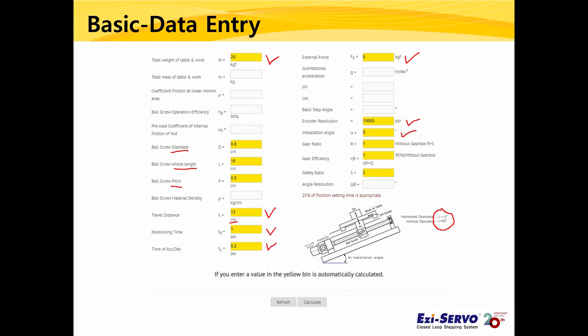This example does not use a gearbox, but if you do, you can enter the gear ratio. Enter 10 for a 1:10 ratio, and 18 for a 1:18 ratio. For gear efficiency, a planetary gearbox is generally 90%, so enter 0.9. A two-stage planetary gearbox would be 0.9 × 0.9 = 0.81. A worm gearbox has a general efficiency of 50%, so enter 0.5. Since this example has no gearbox, enter 1 for both gear ratio and gear efficiency.